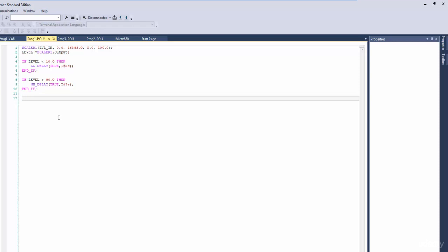So now, once I've got my timer that times out, what do I want to do? Well, I want to create a trigger. I want to one-shot something, and then I want to go ahead and set both my alarm and notification bits for that thing. So how do we do a one-shot in here? Well, we don't have anything, if you remember, from our ladder that's called a one-shot. In here, those are called pulses. And we've got rising edge pulses and we've got falling edge pulses.